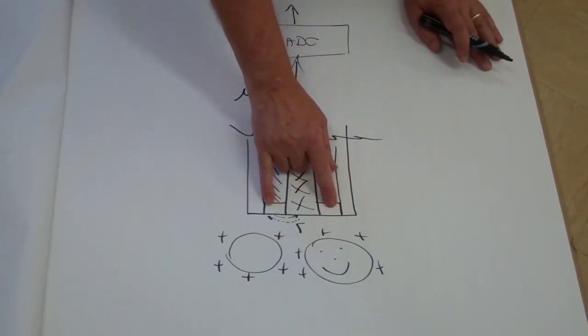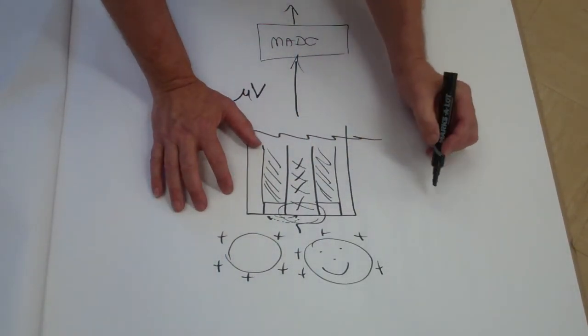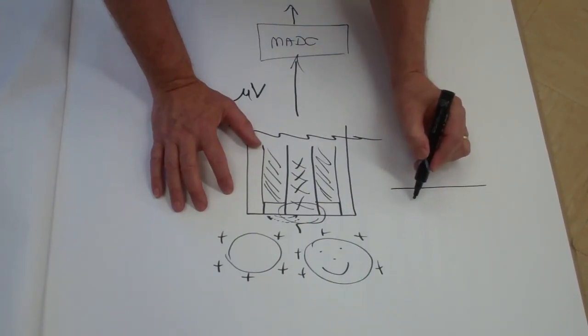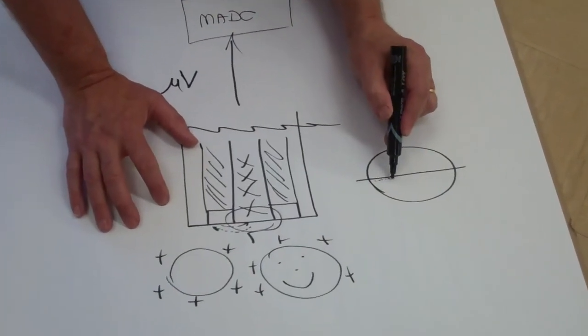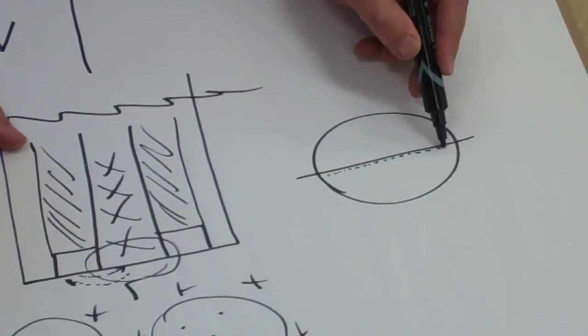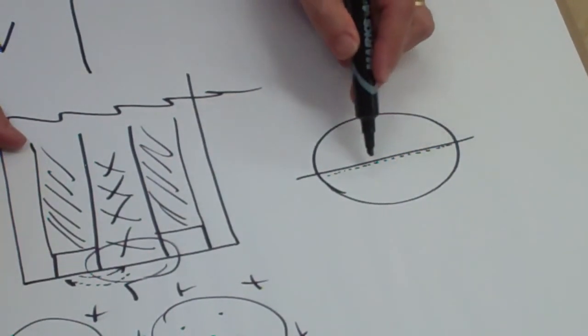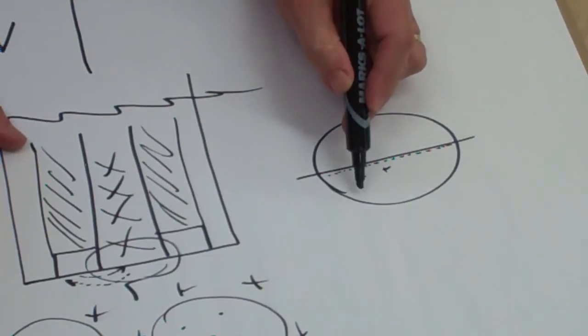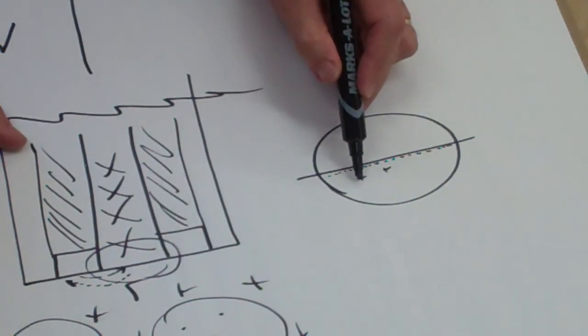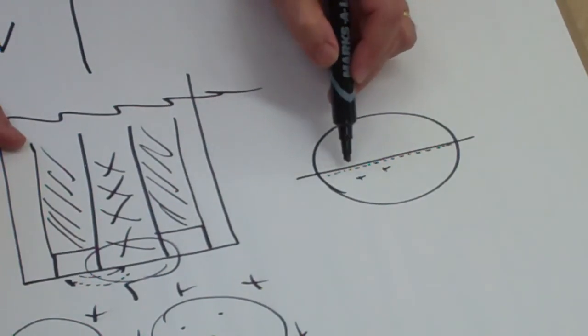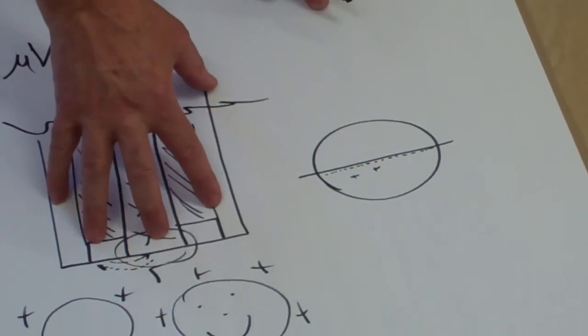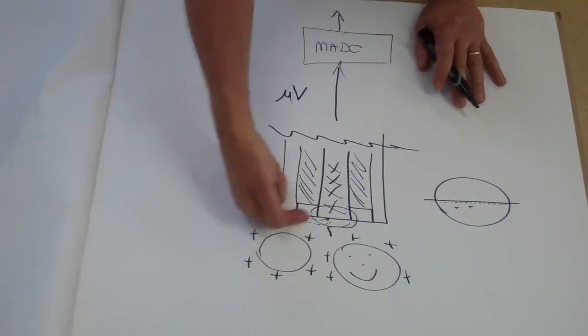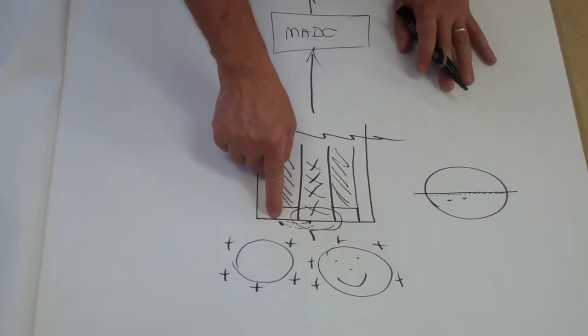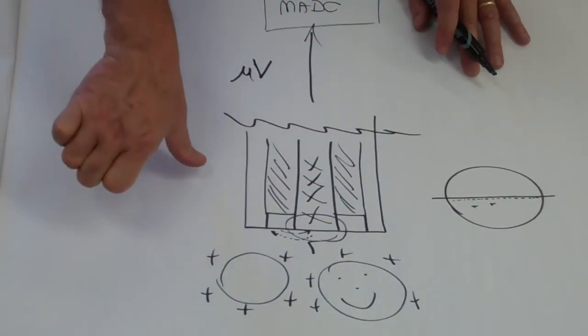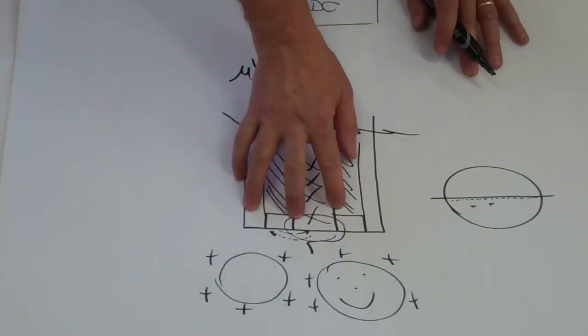Anyways, the nature of pH, there's a glass membrane here. There's a plastic filler. If I was to take this membrane and blow it up really huge, there is a film on the glass membrane. And the glass is semi-porous. The film is designed so when these ions come near it, it allows electrical charge to flow through the glass. What does this mean? This means if you have a probe and you take the ink away, let the air come in and let the air dry on this, there's a film on here. The probe is no good. It's down. It's no good. You got to keep pH probes wet all the time.